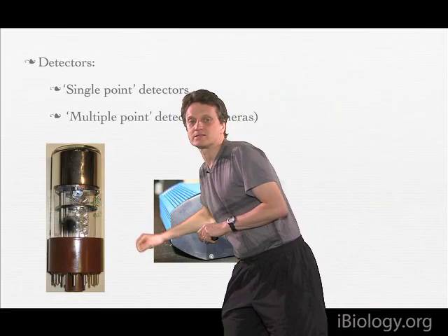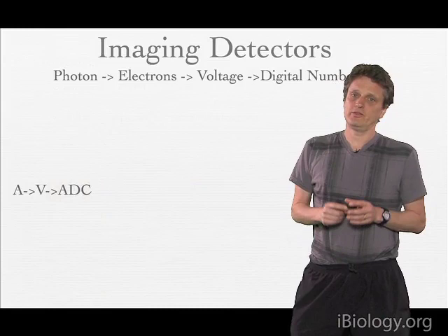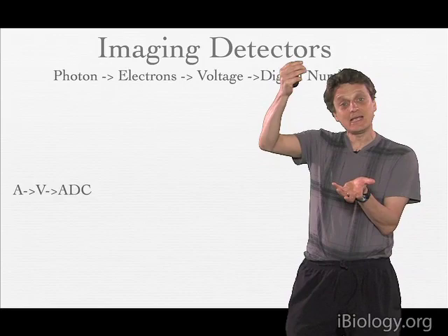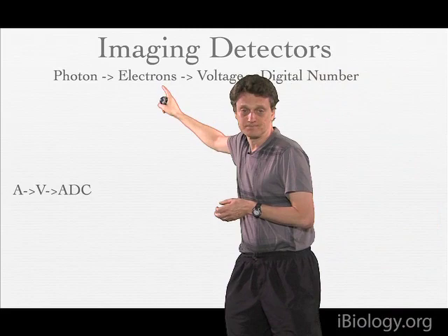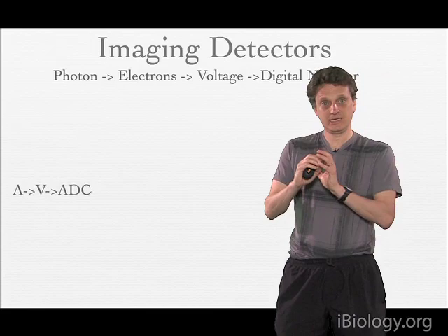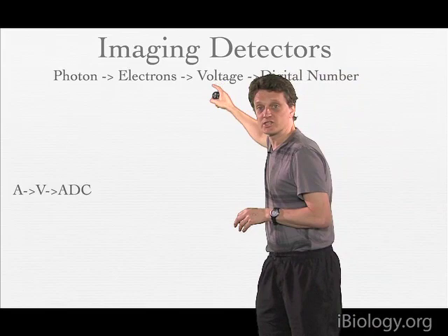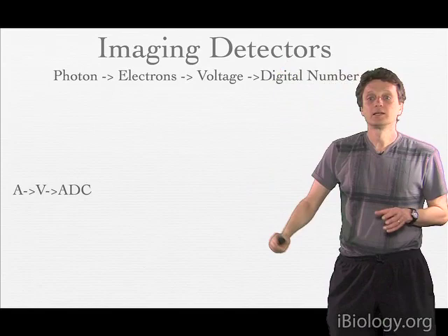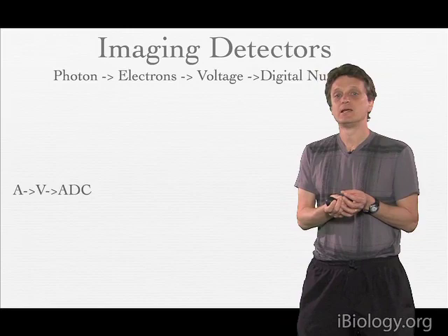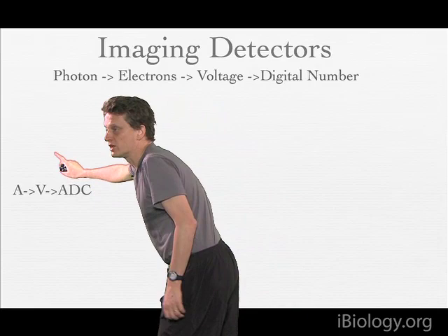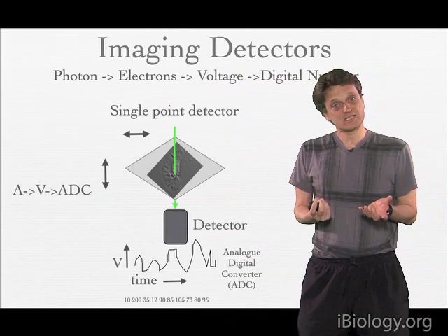Here you see an example of a single point detector — this photomultiplier tube — and here is a camera. All these types of detectors share the same principle: they take in light in the form of photons and convert that into electrons through the photoelectric effect. The number of electrons is converted into a voltage, which is then converted into a digital number that is transported into the computer to build up the image. There is always the sequence: charge to voltage to digital number.